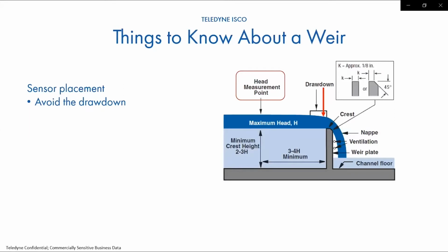And then, so in this case, if you expected 1 foot of head height going over the top of that weir, you want to make sure that your level measurement point is 3 to 4 feet in front of the crest or the weir wall. Now the drawdown, as shown here, you want to avoid the drawdown, and that's why you place the sensor back 3 to 4 times from that weir, because you'll have the drawdown effect. If you have it too close, then you can actually be in the drawdown, which would give you a lower level and thus lower flow rates.